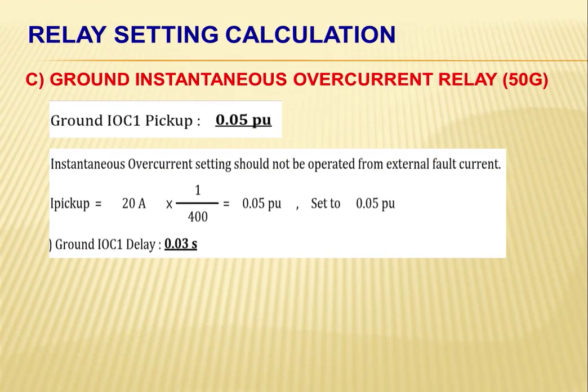Next, we will be calculating the ground instantaneous overcurrent relay setting, or 50G. This relay is connected to the zero sequence current transformer, which is also connected to the grounded neutral of our station transformer. For that, we're going to limit the ground fault current to be less than 20 amperes. That's why here we assign the pickup current to be 20 amperes.